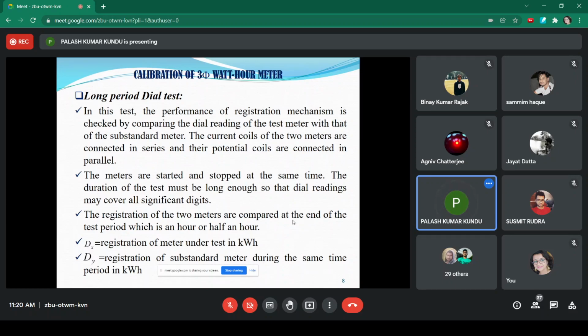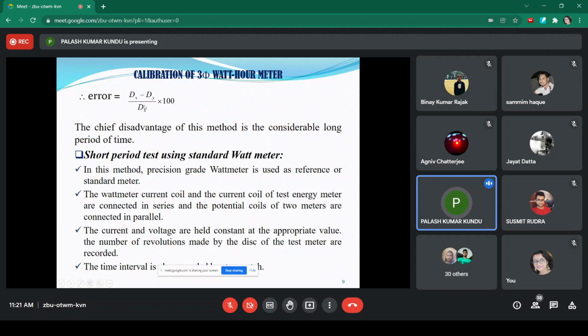In this test, long period means 30 minutes, or more than 30 minutes, say 45 minutes. A fixed time should be used, over which the readings of the meter, which are directly available from the decade dial system, should be noted. Without counting the disc rotations, the meter readings of the substandard meter and the test meter are noted down. And using the formula like this, the percentage error for the long duration test is calculated.